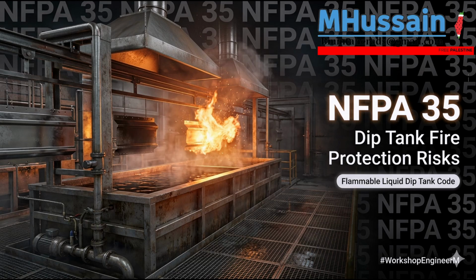The Danvers incident. Yes, in 2006 in Danvers, Massachusetts. An ink and paint facility was heating a mixing tank overnight. The primary temperature control failed, the heat stayed on, and the tank boiled uncontrolled for hours, completely filling the building with vapor. And then? A spark eventually ignited it, and the explosion leveled the facility and damaged dozens of homes nearby. Following the forensic analysis, the NFPA updated these codes to mandate these automatic, redundant, high-temperature shutoffs. It is the grim reality of industrial safety codes. They are often written in the ashes of past disasters.